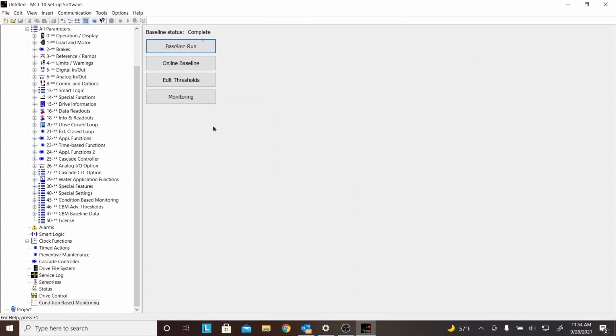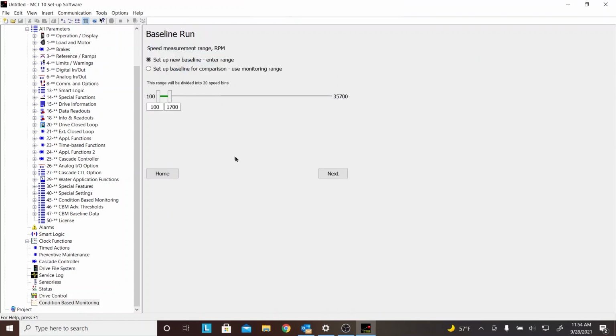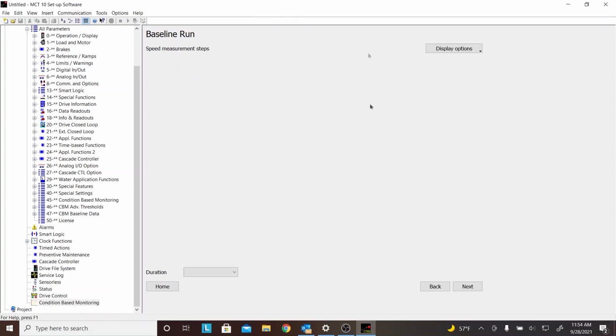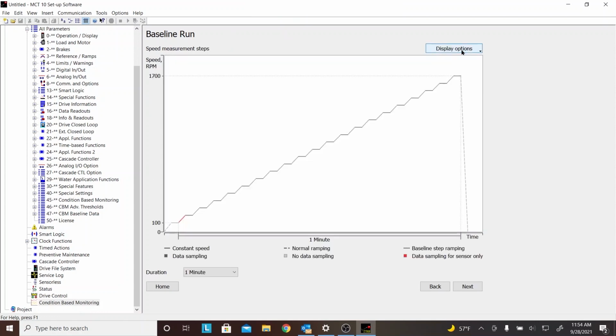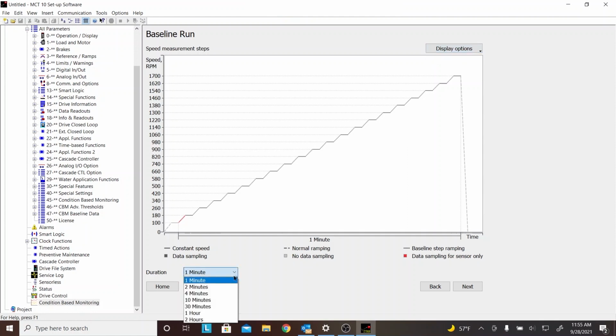But we're going to do a manual baseline because this is a demo and we only have so much time. So I'm looking at setting up a baseline. At this point, I'm just going to pop the values in. We are going to measure between 100 and 1700 RPM on the motor. We're going to pick 20 points out of there. It's already chosen for us. The software is going to gather all this data and store it into our baseline data. We are going to do that manually in a minute.